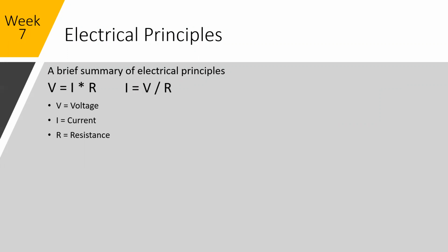The other equation of the power triangle, as they put it, is I equals V over R. This is the universal calculation that you need to know, because when you're checking drawings, it's very important to be able to quickly confirm if your equipment is sized properly. Do you have the right breakers for the circuit that you're looking at, especially if you're in an engineering environment where you're building panels, you're supplying fusing, you're supplying protection equipment for specific pieces of equipment.